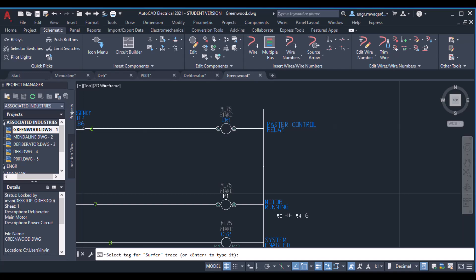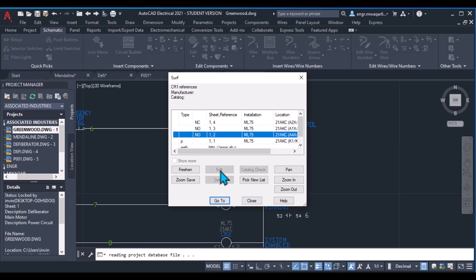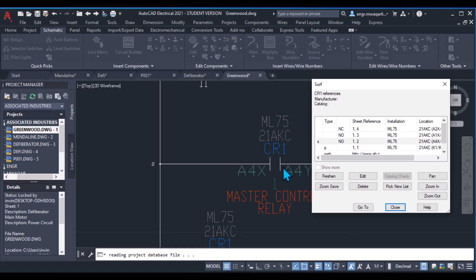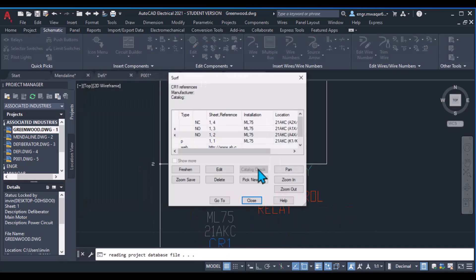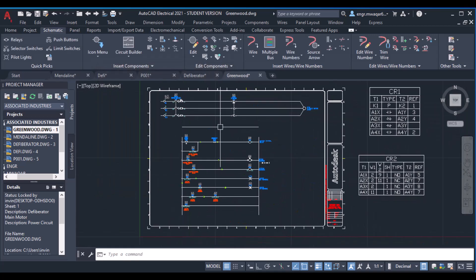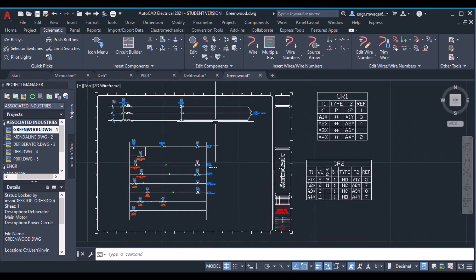Just click Surfer Trace to check the Surfer trace. You will find that it has a normally open contact — these are the child components, the parent is on one sheet, and that is my reference number. These are the two normally open contacts used in my list, and that is my normally closed contact. You can go to that component directly from here. This is a very important function — the Surfer/Trace command — where we can trace cross-referencing to see where our components are connected and on which sheet. When we have multiple drawings with hundreds of sheets in a project, we face such problems and need to trace all the cross-referencing details efficiently.